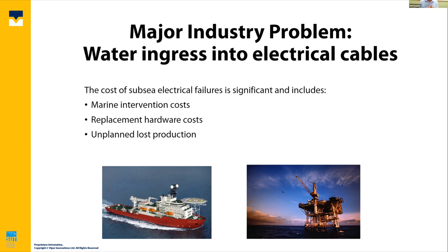So you have low insulation resistance. Maybe the insulation resistance is stable. Maybe it's 100 kilo ohms. It's stable, and your system's operating, so I'm going to keep an eye on my insulation resistance. But then, bang, all of a sudden you lose power to subsea without any prior knowledge. While you've had a low insulation resistance, you've slowly been corroding the copper, and it ultimately turns itself into a fuse, pops open and goes open circuit. At that point, you have no option but to replace the cable or the umbilical.